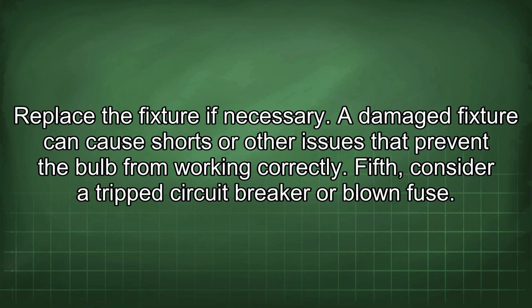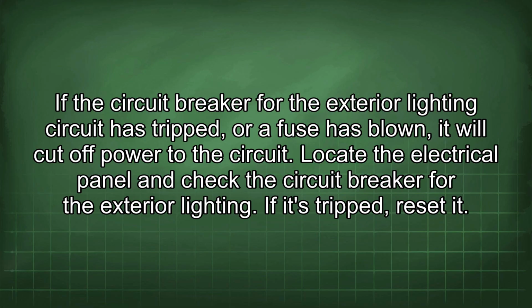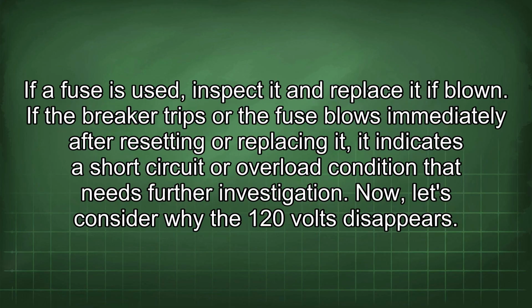Fifth, consider a tripped circuit breaker or blown fuse. If the circuit breaker for the exterior lighting circuit has tripped or a fuse has blown, it will cut off power to the circuit. Locate the electrical panel and check the circuit breaker for the exterior lighting. If it's tripped, reset it. If a fuse is used, inspect it and replace it if blown. If the breaker trips or the fuse blows immediately after resetting or replacing it, it indicates a short circuit or overload condition that needs further investigation.